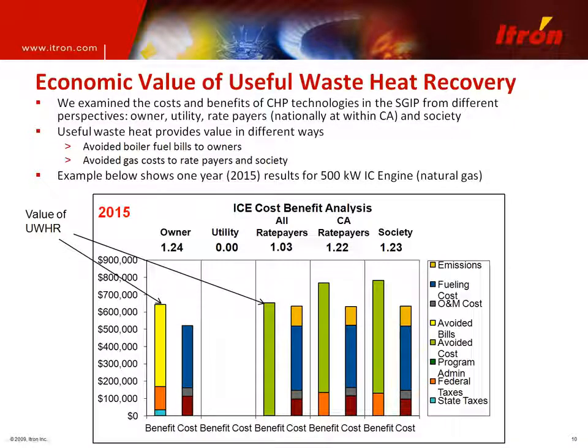So you can, again, gain huge benefits to the owner by achieving useful waste heat recovery. We didn't run a utility case in this particular instance, so that's why you see a zero value for the utility. But in terms of ratepayers and society, again, the green bars represent the benefit from those perspectives, and that's really made up of a combination of some reduced gas transportation costs as well as energy costs that are saved from electricity displaced by electric chillers. So again, you can see useful waste heat recovery has substantial economic value.